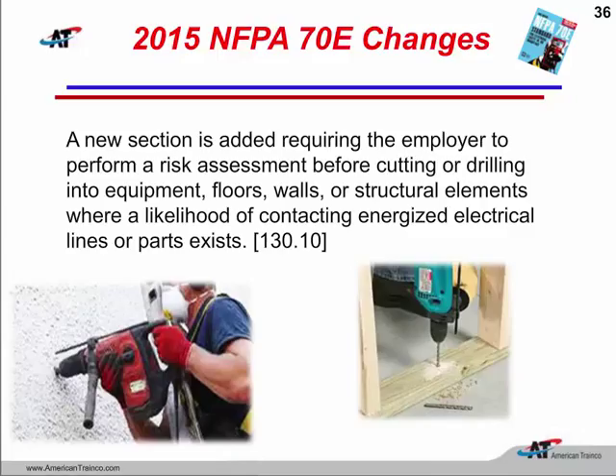A qualified electrical worker was fairly knowledgeable about this particular motor control center, and they decided to take a hole saw and drill through the outside metal to maybe install a connector of whatever size. Well, what they did not realize was how that motor control center was constructed, because behind the piece of metal that they were drilling was a chase for the conductors that feed that MCC.